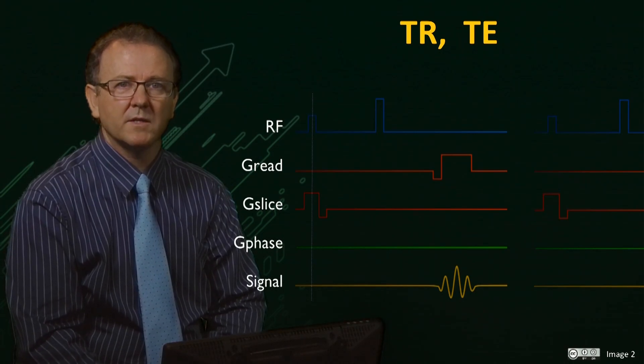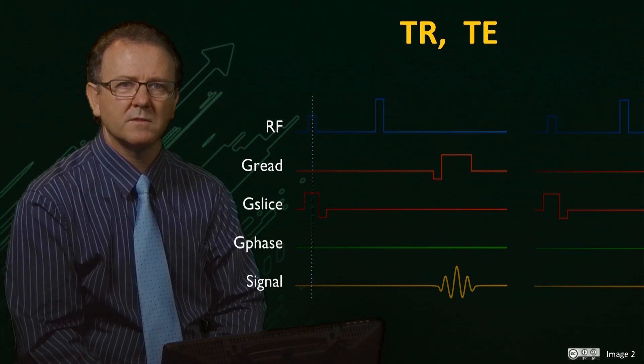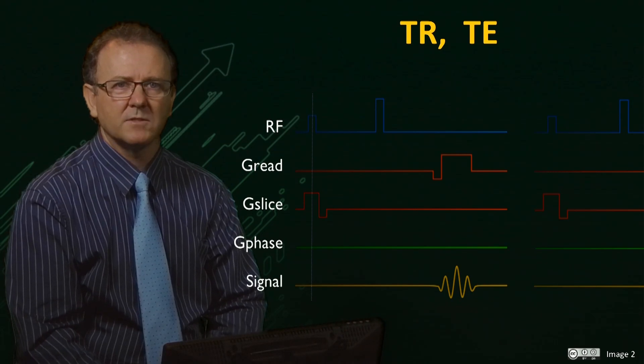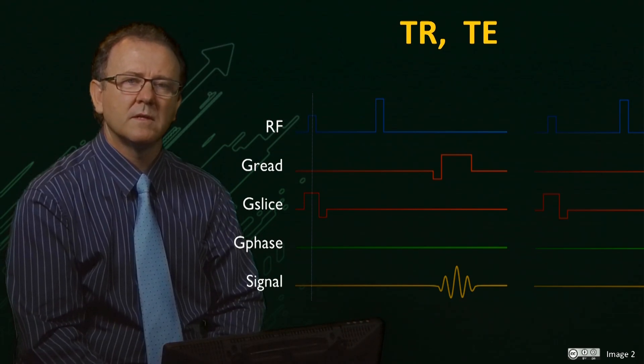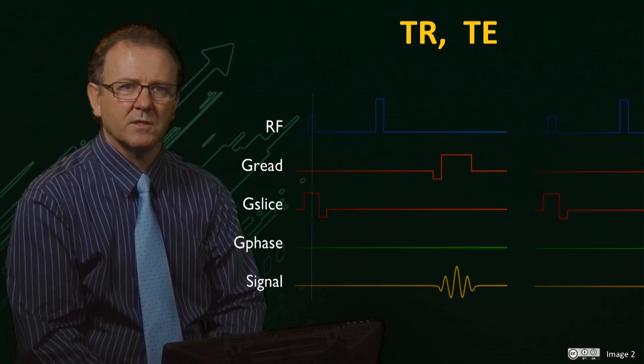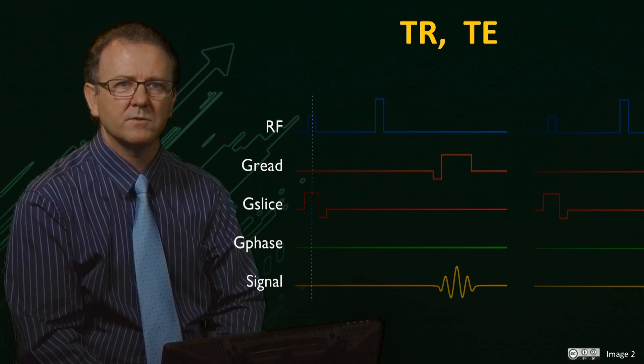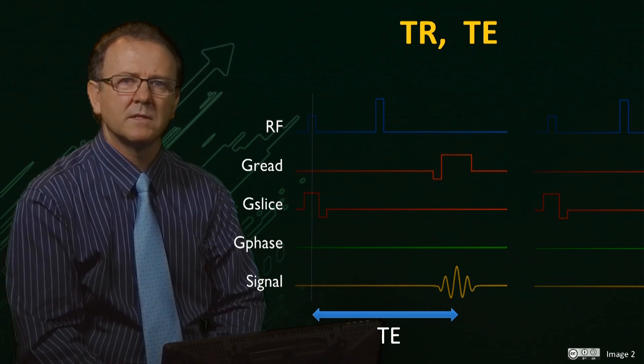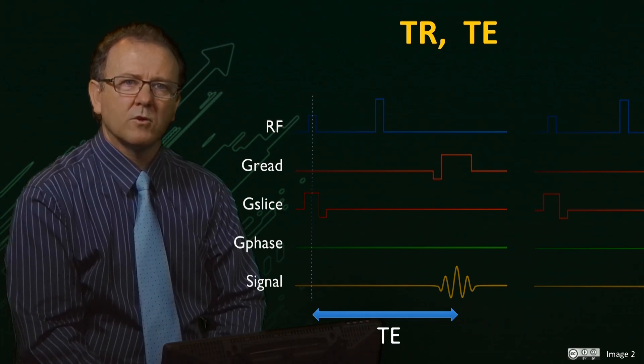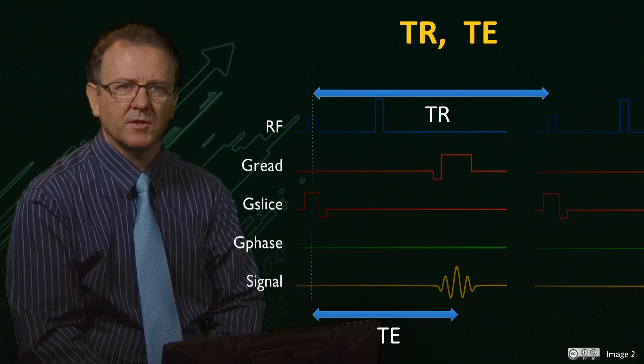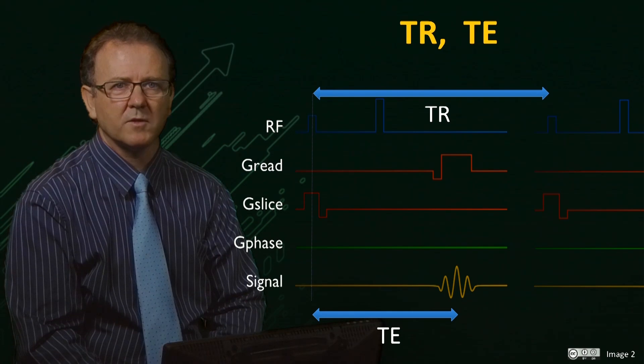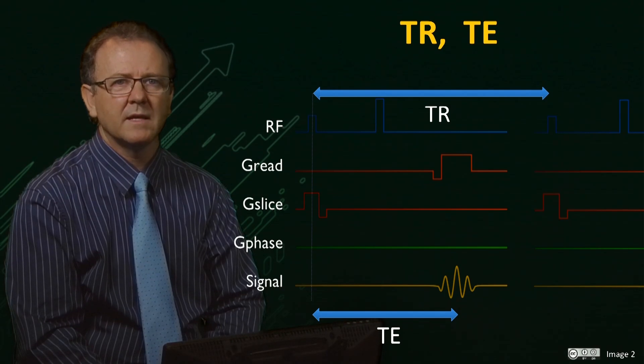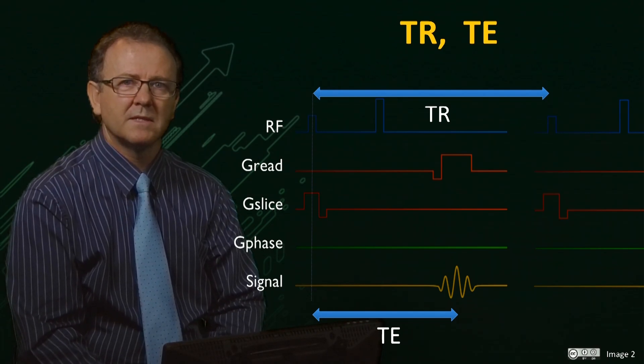Before considering the effect of relaxation we should remind ourselves of the two imaging sequence parameters that affect the times available for relaxation to occur during the sequence. Here is the spin echo imaging sequence we have described before. The period during which transverse relaxation occurs is between the 90 degree excitation pulse and the maximum of the echo that is formed by the 180 degree refocusing pulse, TE. The longitudinal relaxation occurs immediately after the 90 degree pulse and continues until the 90 degree pulse of the next phase encoding step is applied and includes the time for the spin echo to be acquired and any waiting time between the increments. This is TR.